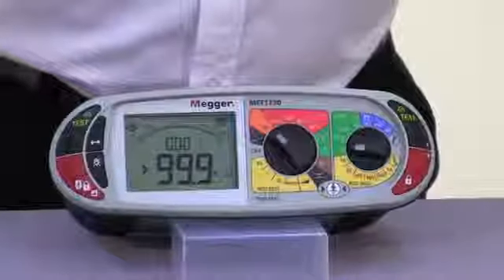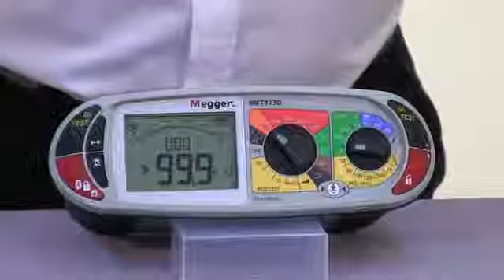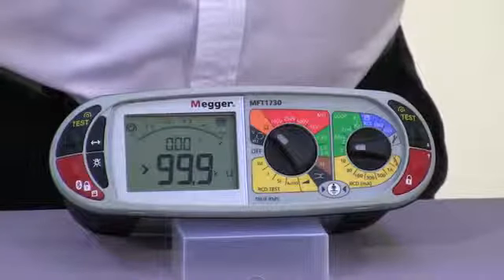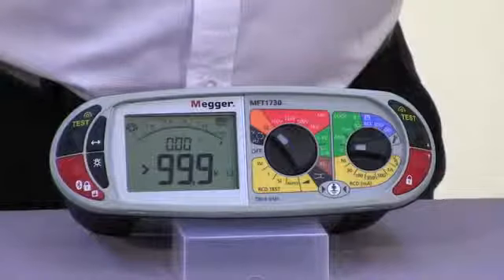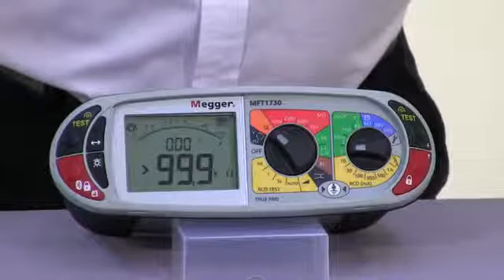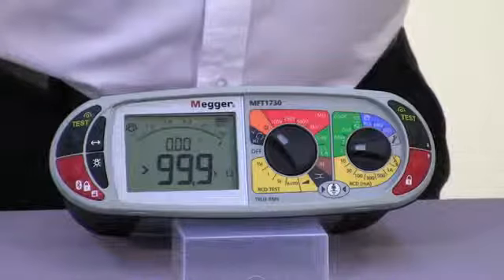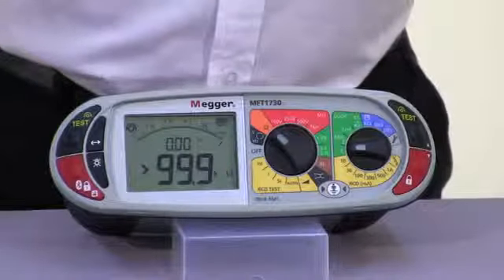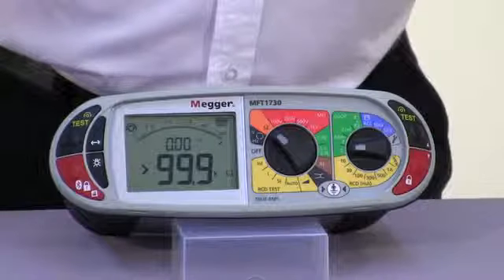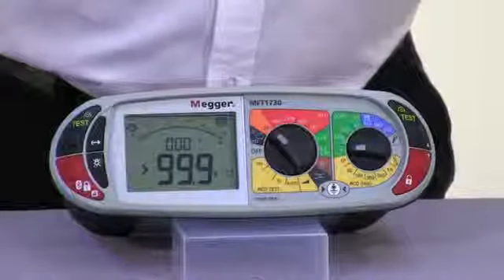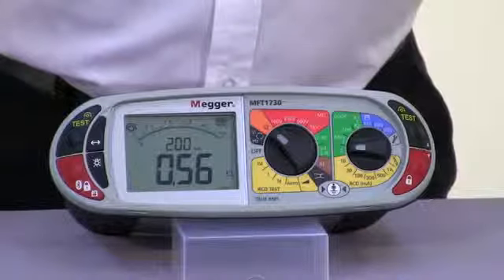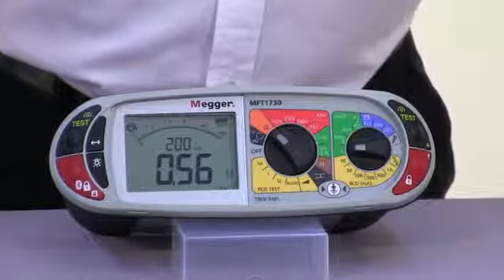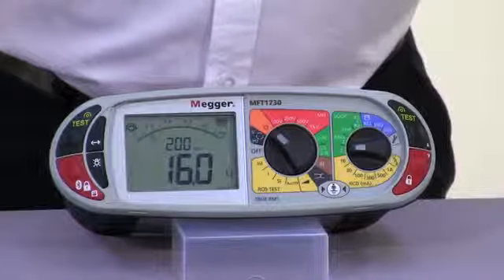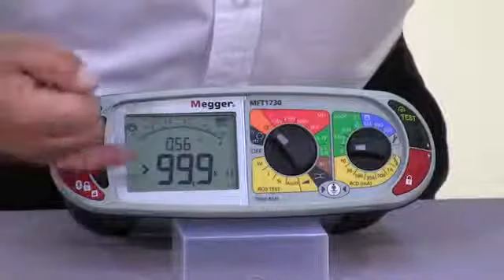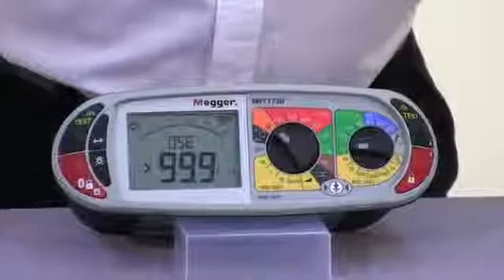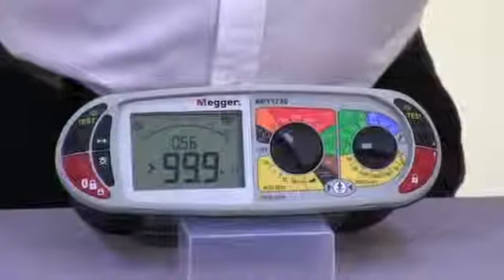Okay, so having nulled out the leads, what we'll do now is take a straightforward continuity measurement. Now one of the nice features on the 1700 series is that once you've got a stable reading, you get an audible indication. So if you were testing in the top of a distribution board, you wouldn't need to be concentrating on what the meter is doing, as you get a nice beep to indicate that the test has been completed. So when we apply our known value, we get the audible beep, we can remove our probes from the test circuit, and as you can see, the reading has now been transferred and is displayed on the upper of the 2 parameter display.